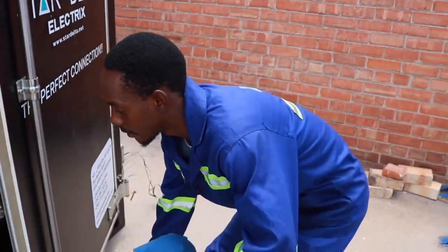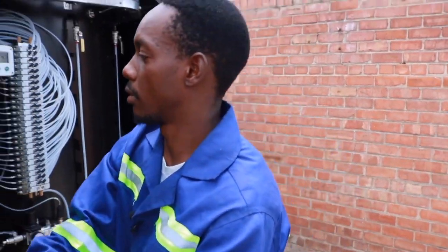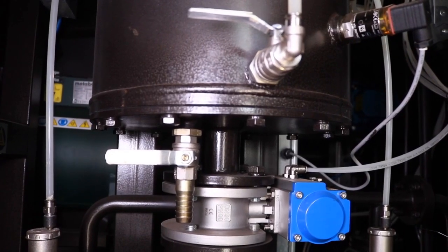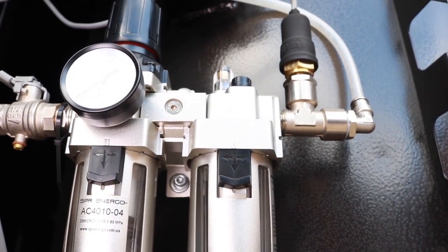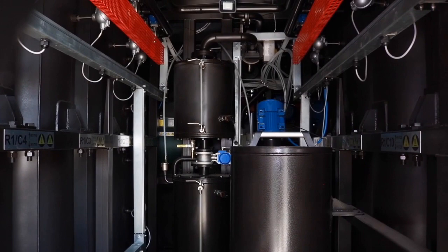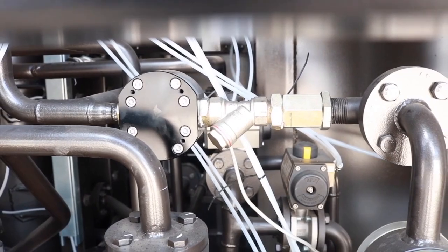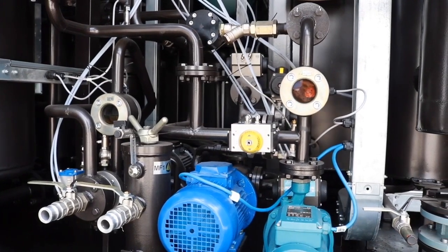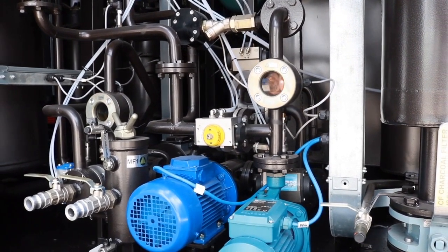You can actually connect it directly onto the transformer, so instead of draining, you can connect it direct. The advantage this has is a dislodging property, because over a period of time, sludge builds up inside the windings of the transformer. This machine is able to remove the sludge that has built in. But when you're just purifying, you drain out the oil, and a certain amount of oil remains in the transformer. Also, the capacity of our machine can go up to 6,000 liters per hour.